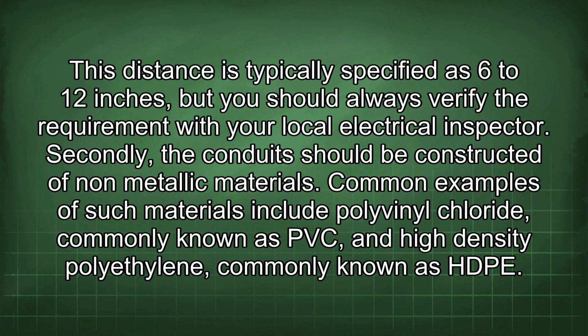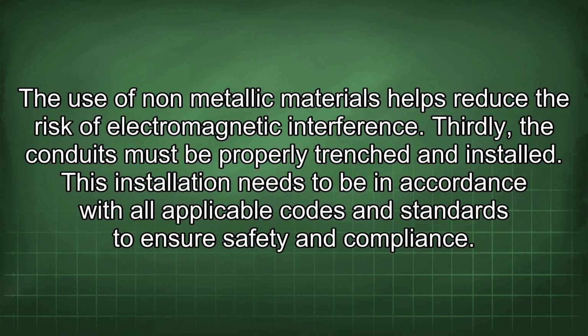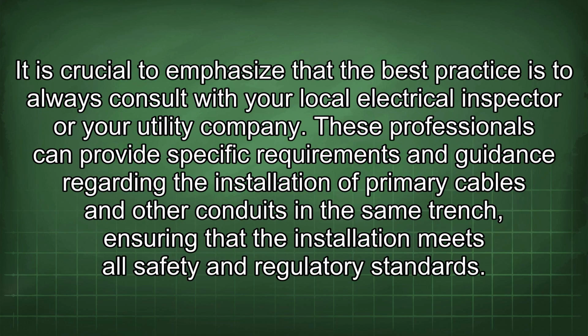Common examples of such materials include polyvinyl chloride, commonly known as PVC, and high-density polyethylene, commonly known as HDPE. The use of non-metallic materials helps reduce the risk of electromagnetic interference. Thirdly, the conduits must be properly trenched and installed. This installation needs to be in accordance with all applicable codes and standards to ensure safety and compliance. It is crucial to emphasize that the best practice is to always consult with your local electrical inspector or your utility company. These professionals can provide specific requirements and guidance regarding the installation of primary cables and other conduits in the same trench, ensuring that the installation meets all safety and regulatory standards.